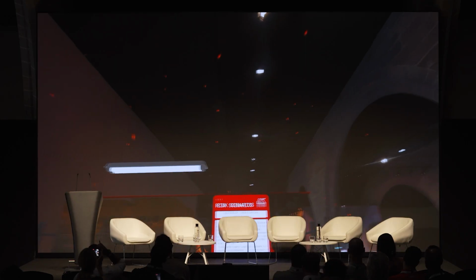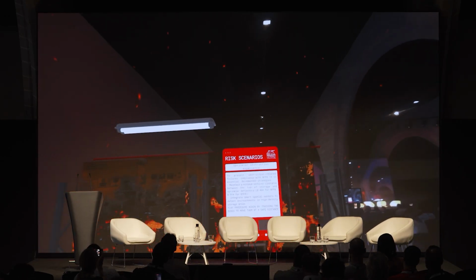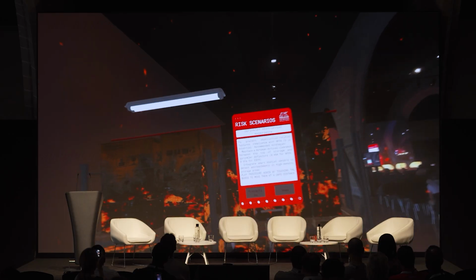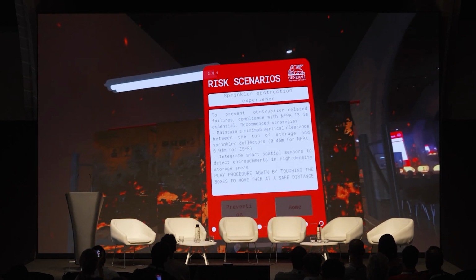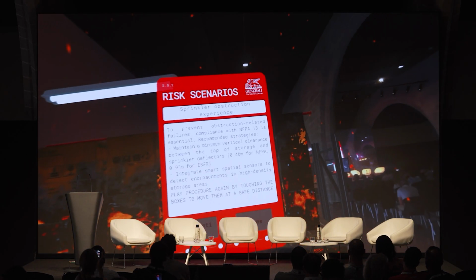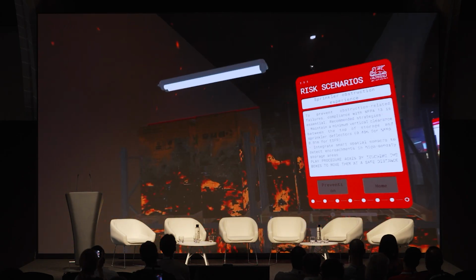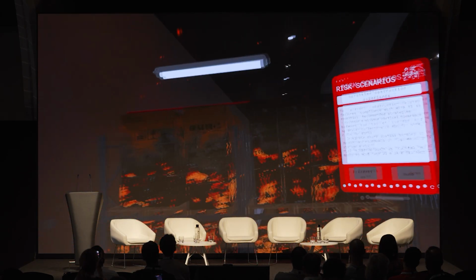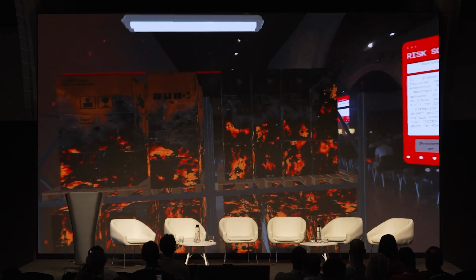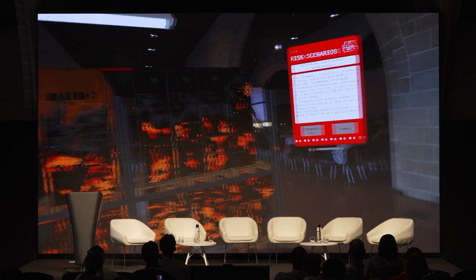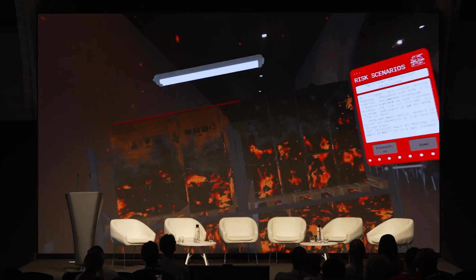To prevent obstruction-related failures, compliance with NFPA 13 and NFPA 25 is essential. Recommended mitigation strategies include maintaining a minimum of 457 millimeters vertical clearance between the top of storage and horizontal sprinkler deflectors, conducting regular obstruction assessments as part of quarterly fire system inspections, and training facility staff on passive sprinkler obstruction, including unapproved signage, lighting fixtures, or seasonal decorations.